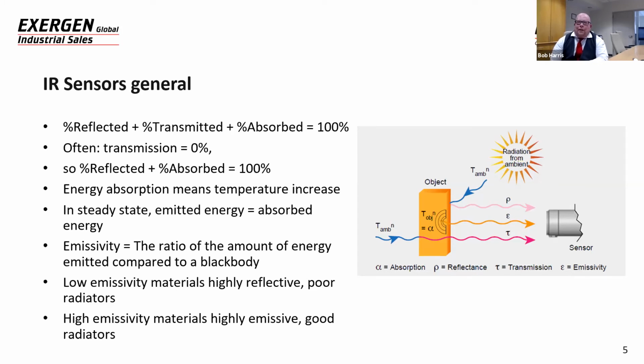And there's a term called emissivity in the industry, which is defined as the ratio of the amount of energy emitted compared to a black body. And a black body is a perfect emitter. So materials will either be low emissivity or high emissivity. The low emissivity materials are often shiny metal surfaces, and they are very poor radiators. The high emissivity materials are highly emissive, and they're good radiators. A coated metal would also be a high emissivity material. So those are the types of objects that we have the best luck measuring. Of course, we can measure anything, and every object will emit energy, but the high emissivity materials are the best radiators.